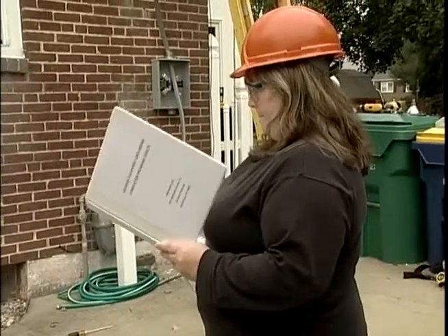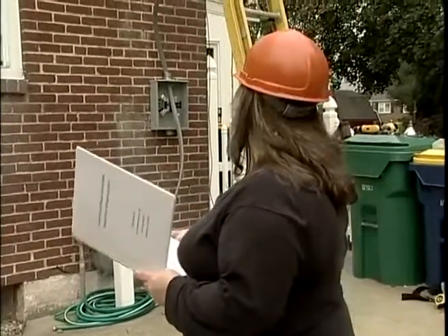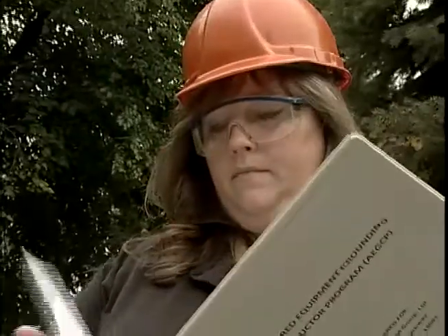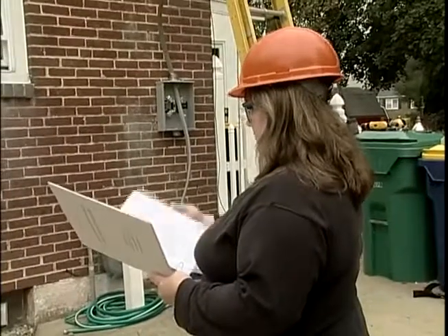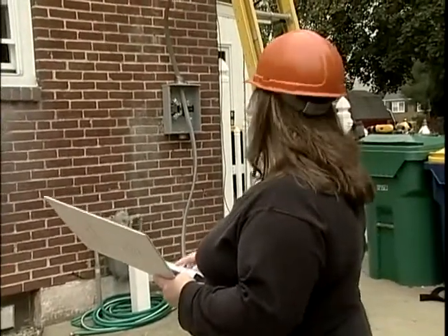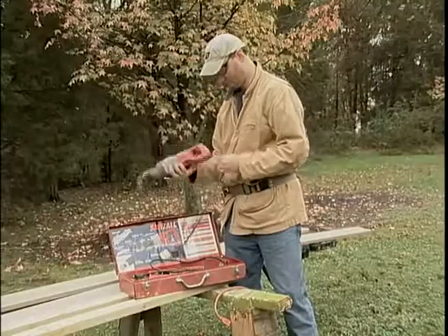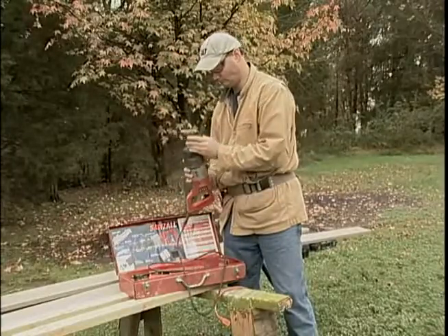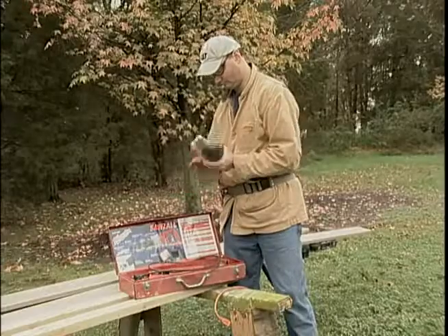If, for some reason, GFCIs can't be used on a job site, an Assured Equipment Grounding Conductor program can be implemented. This program must be implemented by a competent person, designated by the general contractor or builder responsible for the project. The program must be designed so that all of the electrically powered tools and equipment on the site have some type of grounding protection.